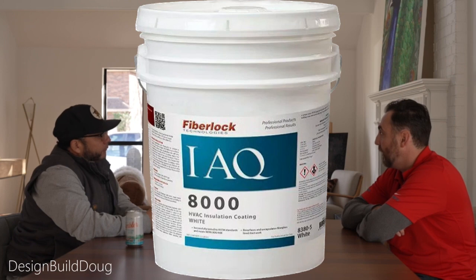They also make encapsulant paints that can be spray applied, and those provide a nice even coating. They have natural antimicrobial properties. It's sort of a rubberized coating similar to mastic, but mastic is more for duct sealing, whereas this is a product you could spray on a plenum after installing it. That helps with the sponginess and keeps everything on the surface, so if a water droplet comes off the coil, it has a chance to re-evaporate instead of sinking into that sponge. So there are some solutions.